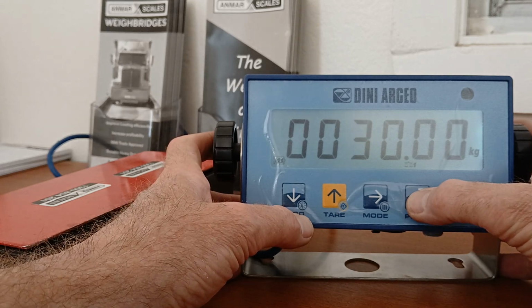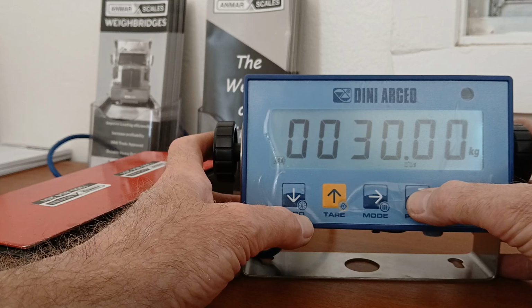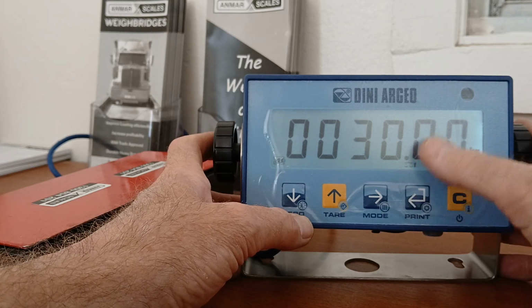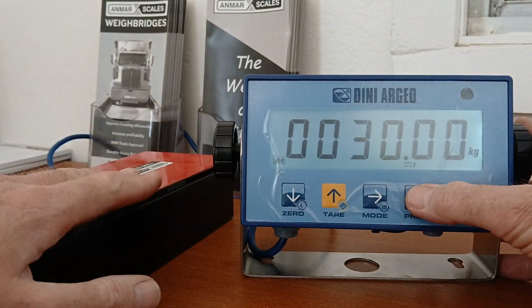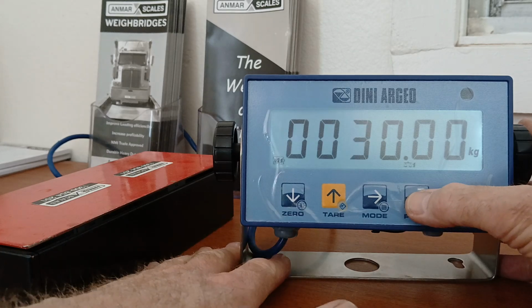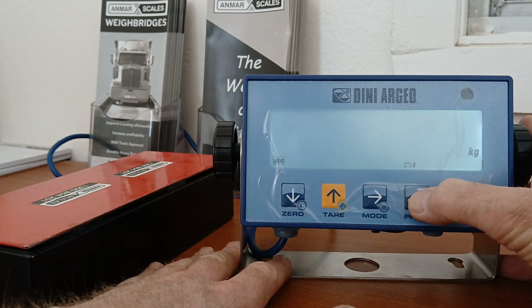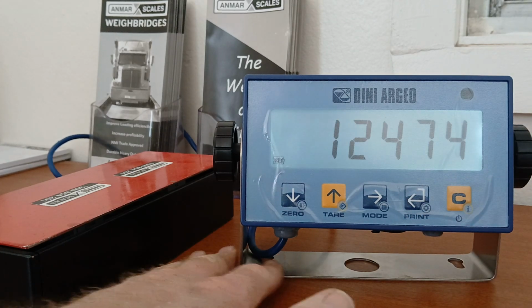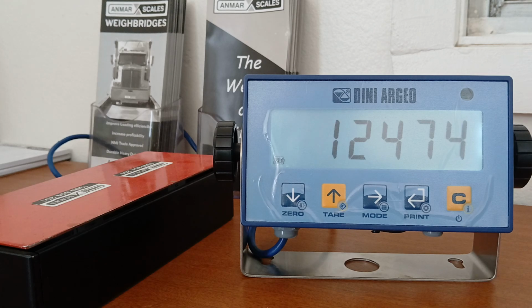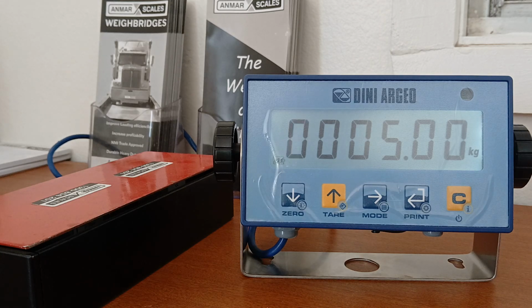Once we do this, the scale will automatically perform a zero calibration. So we need to make sure that the scale plate is empty and nothing is on it. So we push enter. It says unload, and then it flashes some numbers for a few seconds. It says OK, and that is our zero calibration done. It's now flashing, asking for a calibration weight.